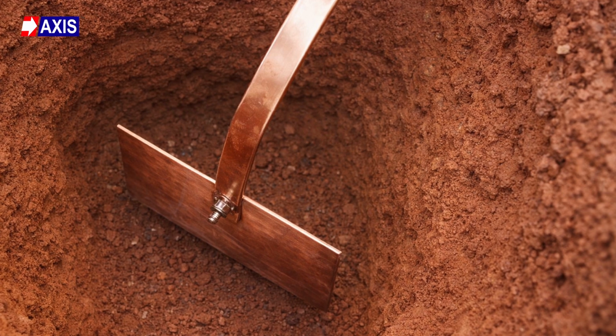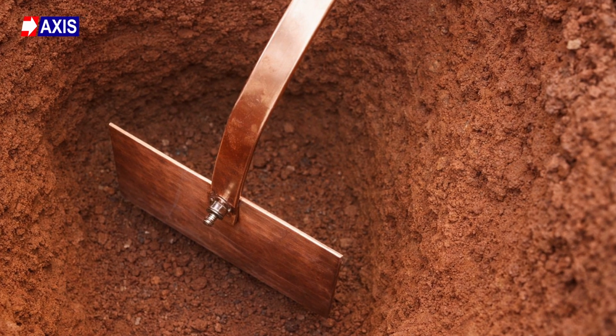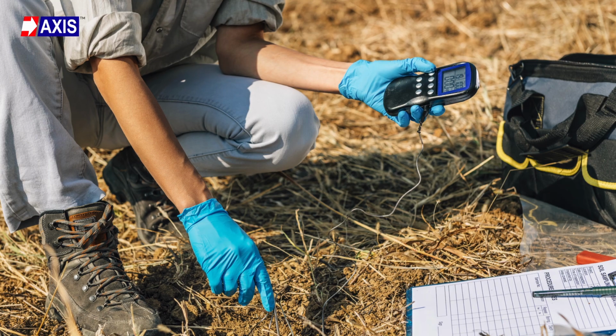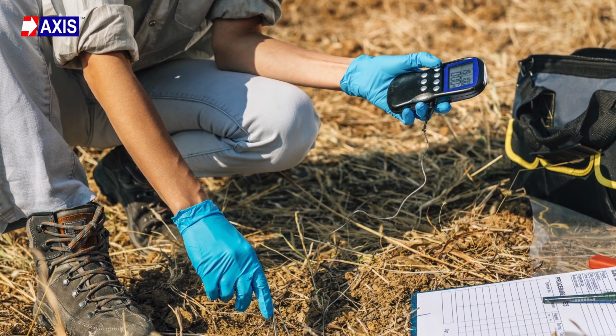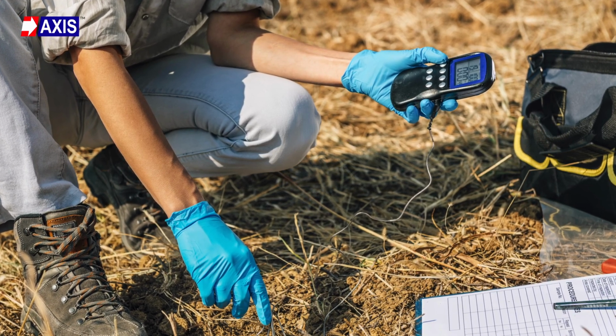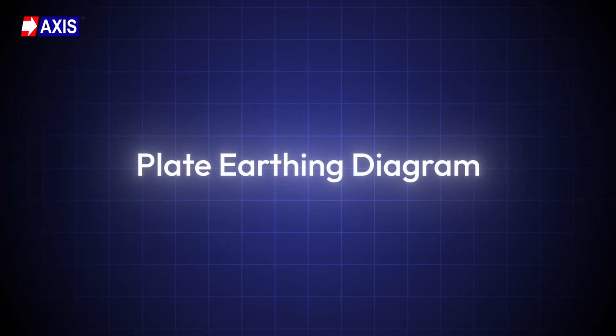In plate earthing, you place a metal plate in the ground at a fixed depth. The plate is usually buried about 3 meters below the surface, so it stays in contact with moist soil. This plate connects to your equipment through a copper or GI strip, and the soil around the plate must stay moist because moisture keeps the resistance low. The lower the resistance, the faster the fault current moves into the soil. Now let's understand the diagram.